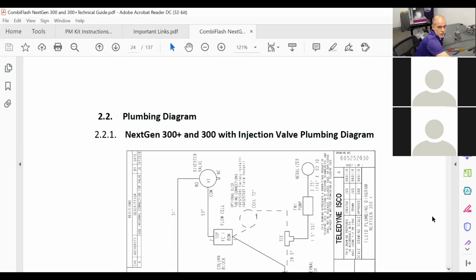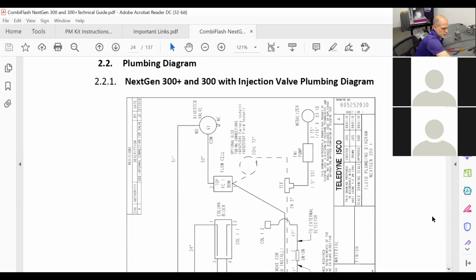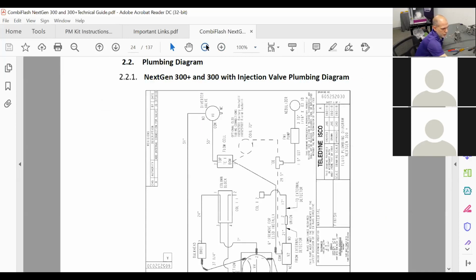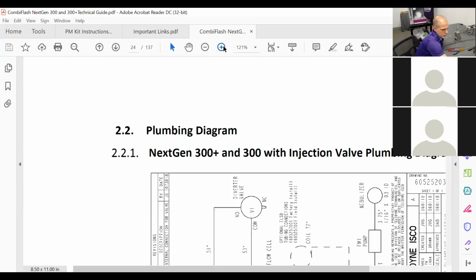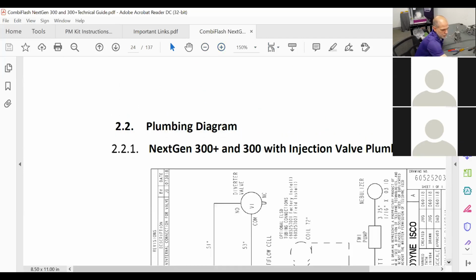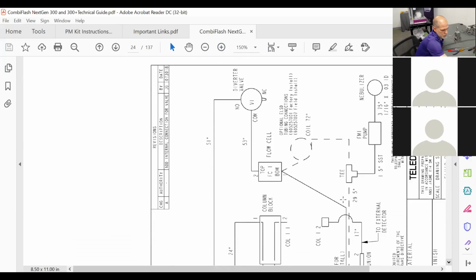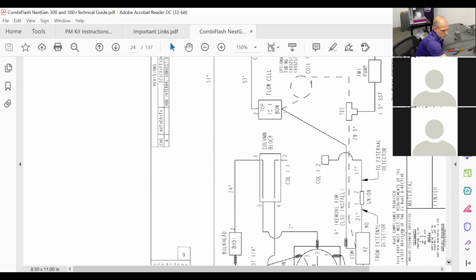So this one's sideways, but this is the NextGen 300 plus and 300 with injection valve plumbing diagram. This is the overall diagram. Oh, that looks terrible. So you've got the diverter valve, flow cell, a spot to mount your column. This bulkhead here is a spot on the unit where there's a tubing line. So if you have a solid load cartridge, it would basically go right here at the top of the column block.